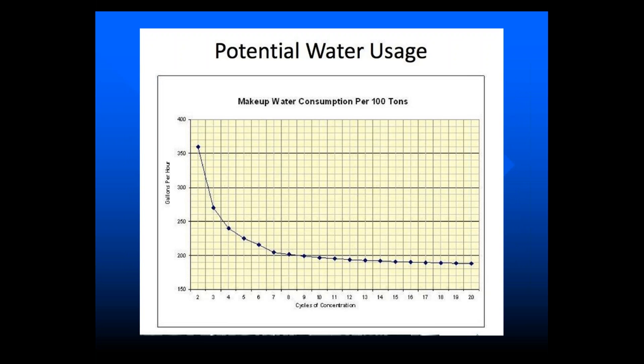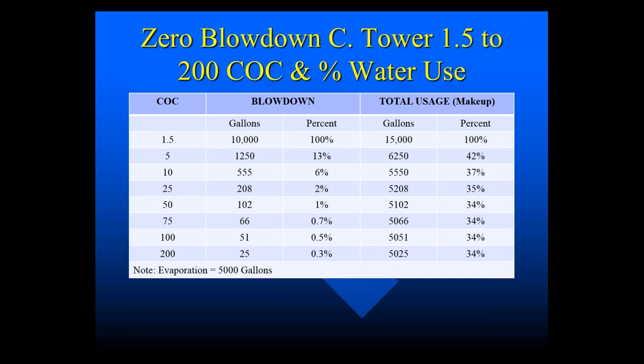This graph shows cycles of concentration versus gallons per hour used. As you increase your cycles, you decrease the gallons used, and by the time you get to 20 cycles you've leveled off. If you go to 10 cycles of concentration you've saved about 35%; going to 25 to 200 cycles, you haven't saved any more water really. So if you're wanting water savings, once you get to 20 to 25 cycles, you've saved all the water you're going to save.